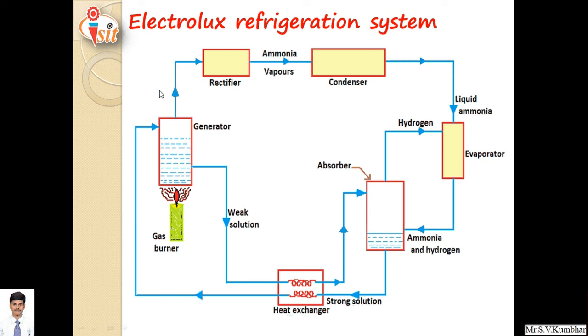Ammonia is used as refrigerant and water as absorbent. Ammonia is quickly converted into vapors and sent to the rectifier. In the rectifier, if water vapor or water droplets are present, they are rectified — only ammonia vapor passes through. The water vapor is collected and sent back to the generator. Only high pressure, high temperature ammonia vapors pass through the condenser where heat energy is rejected, converting ammonia into high pressure low temperature liquid. This liquid is sent to the evaporator where cooling effect is achieved. Hydrogen gas is used along with ammonia in the absorbent so that ammonia is quickly absorbed in the absorber, and this hydrogen gas is recirculated again and again.